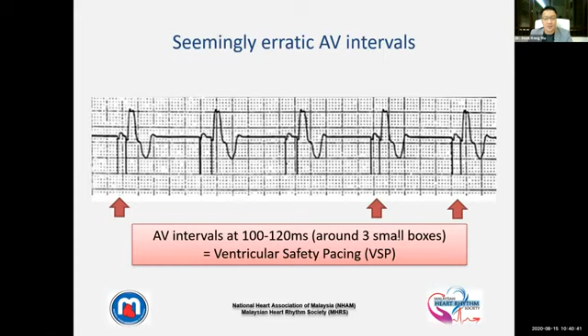Now, upper tracking rate is another term that we need to understand. To put it simply, upper tracking rate is used to prevent, in the event of atrial tachyarrhythmia, where the atrium is beating very fast, the pacemaker trying to catch the rate of the atrium. Now, if you catch the rate of the atrium and pace in the ventricle the same way as in atrial fibrillation or atrial tachycardia, that could be catastrophic as well. As I always amusingly tell my fellows, just imagine the pacemaker is like an accessory pathway. If you do not program it properly, it can behave like an accessory pathway that conducts down to the ventricle in almost one-to-one fashion. So upper tracking rate is designed to prevent that.